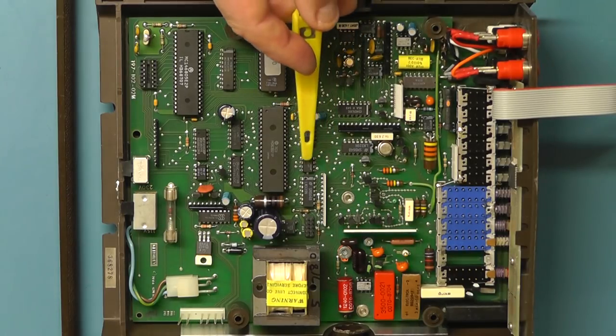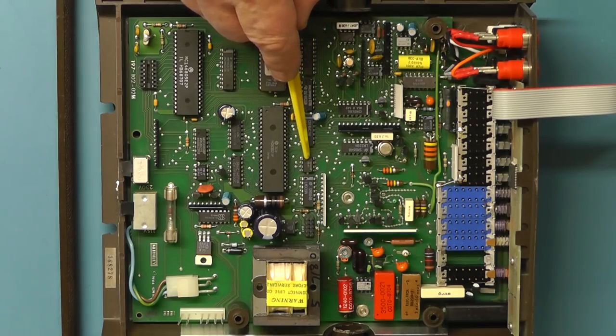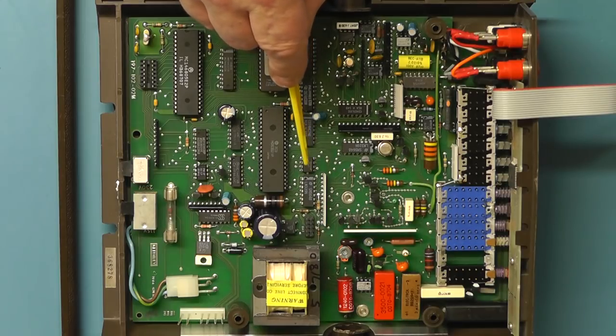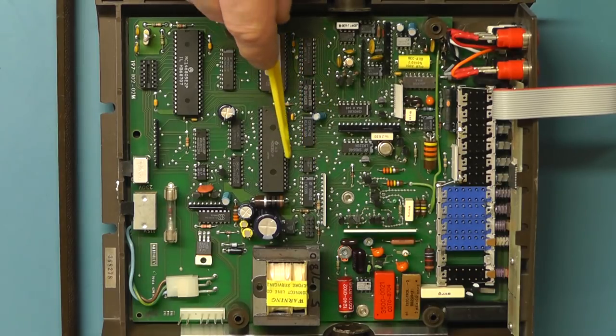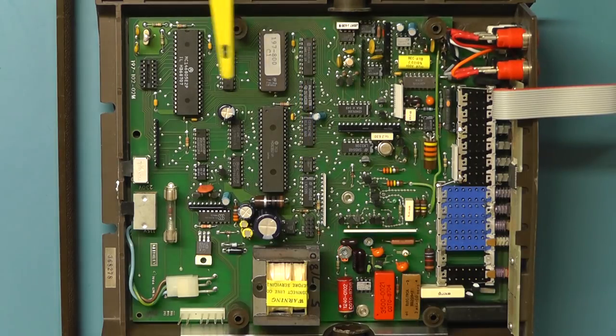The other memory chip you can see there as before is the non-volatile memory there which is electrically alterable and that is used to store the calibration data for the meter. As we saw on the 175 the calibration is done electronically from the front panel and there is no presets within the meter itself.